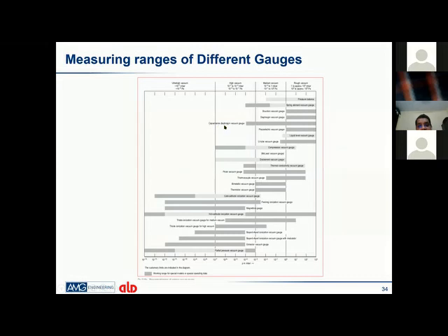We can see the capacitance diaphragm gauge, which is used mostly for LPC activities like low pressure carburizing, where the gases involved are mostly nitrogen, helium, and acetylene. This gauge does not depend on the properties of the gas itself. It works on the pressure which the gas is exerting. It can be used from atmosphere up to -4 and -3 millibar, which is a very good range. So you will find the CDG used in most applications, covering the complete range from the atmosphere to -4, -5.